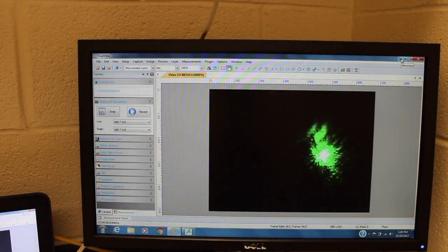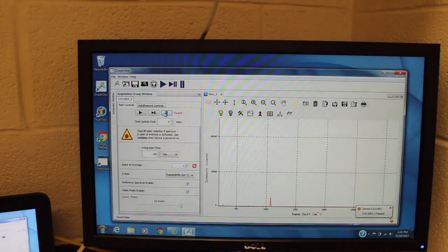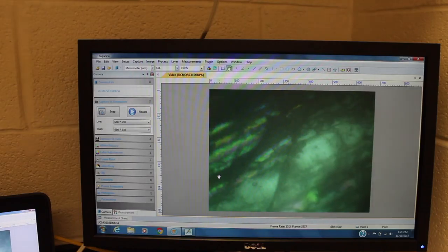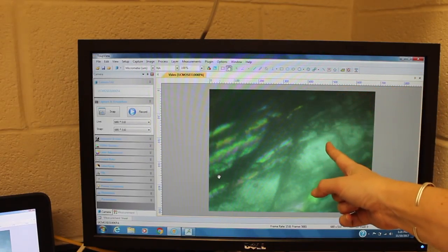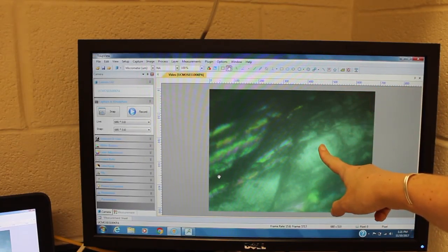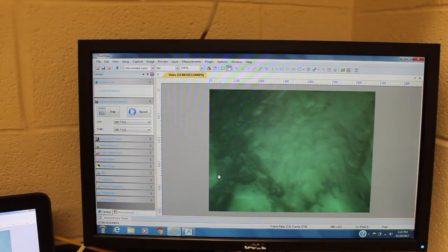So if we wanted to go back and try to refocus to make sure the flattest part of the sample was right there, we would actually go back to the OceanView and stop or pause the laser. And then it's safe to put the toggle back out and turn the light on so that you can see the surface of the sample again, and make sure that at that place, 500 and 250 or so, this place right here is the flattest area.